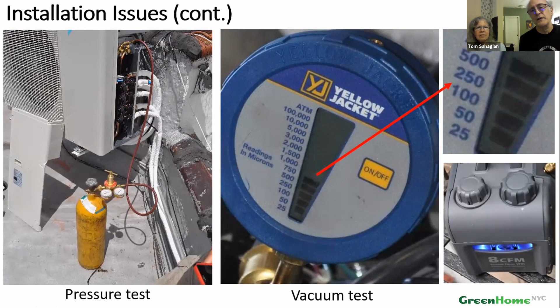Another potential issue, which did not crop up on this job, but when you're using the vacuum pump to do the vacuum test, you've got to make sure that the vacuum pump is set up properly, that the oil is fresh, and that it's the proper number of CFM. You can't just use any old vacuum pump. So there's a lot of little details about doing the right installation that some contractors either don't know about or choose not to follow. And that's why you need somebody on the job to make sure that they follow it properly.